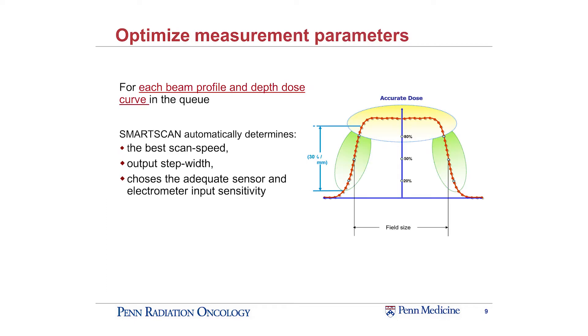For each beam profile and depth-dose curve in the queue, SmartScan automatically determines the best scan speed, the best output step width, and it chooses the adequate sensor and electrometer input sensitivity. This is something I have gone into my clinic and set up manually for each type of scan, but SmartScan does it automatically. It becomes more efficient and will give you higher quality data if you let it select the parameters.